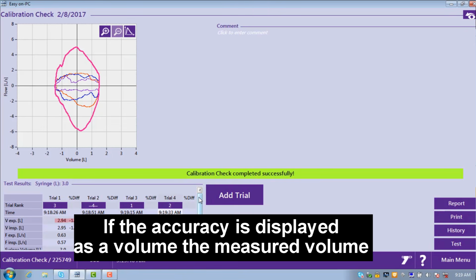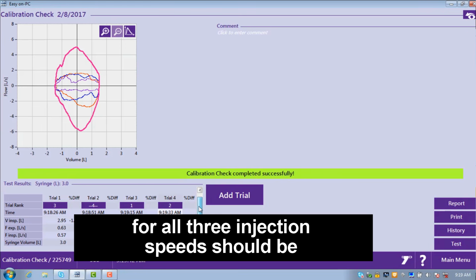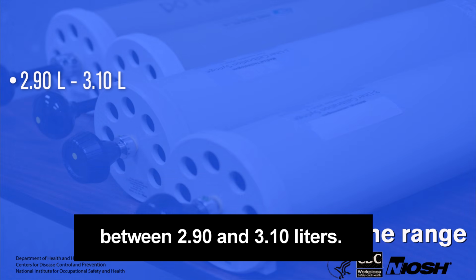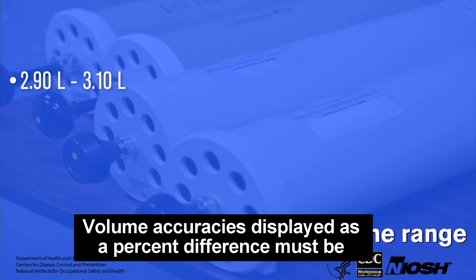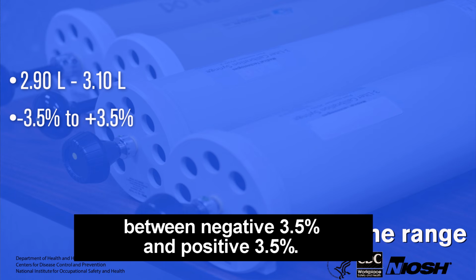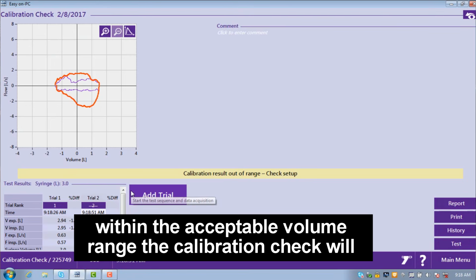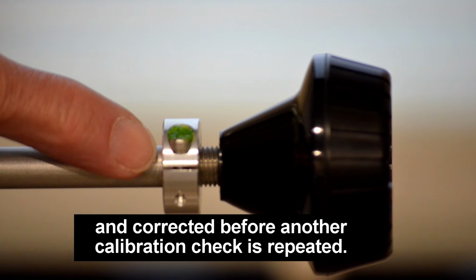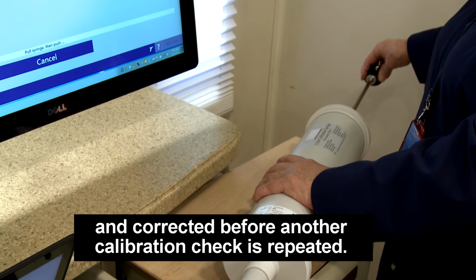If the accuracy is displayed as a volume, the measured volume for all 3 injection speeds should be between 2.90 and 3.10 liters. Volume accuracies displayed as a % difference must be between negative 3.5% and positive 3.5%. If only one volume is not within the acceptable range, the calibration check will have failed. The cause of the failure should be identified and corrected before another calibration check is repeated.